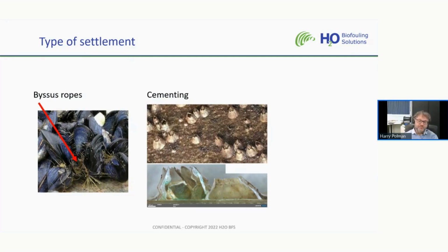Other types of organisms, for example barnacles, you see on the right picture, cement themselves to the surface. Once the larvae attaches to the pipe surface, it creates a calciferous product, and more or less the shell will be glued to the pipe surface. Once these animals are glued, you cannot remove the shells from the surface anymore, only with physical force. If you kill these animals with a biocide or with an effective treatment, you will kill the organism inside the shell, but the shell itself will remain on the pipe surface. That also means that the wall roughness created by these shells, and the head loss caused by that wall roughness, will not be eliminated once you already have settlement of these organisms on your pipe surface.